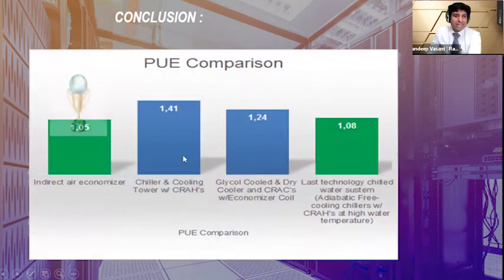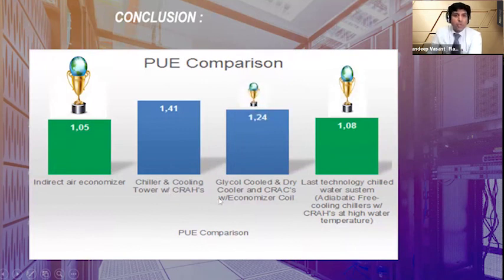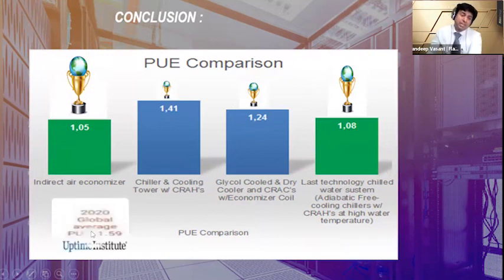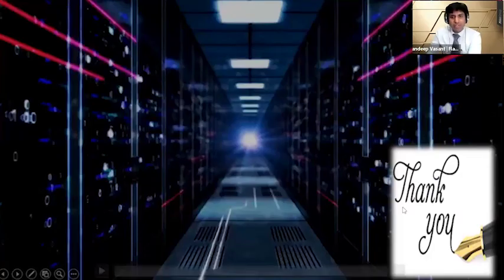To pull back on that same PUE number, with indirect or direct free cooling, the PUE numbers would go down to, as I said, 1.08, again depending upon the type of unit. As I said, the global average is 1.59 as reported by Uptime. Choose any cooling unit, direct or indirect, and the PUE numbers would definitely drop.